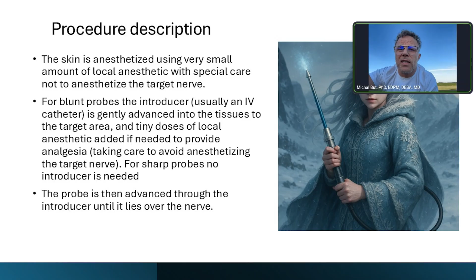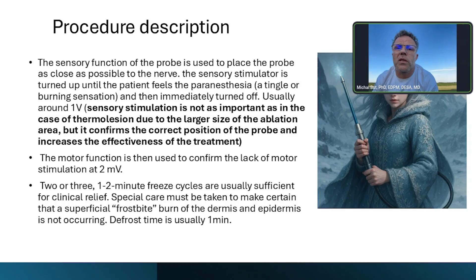And use the stimulation, especially when you start with the procedure. I encourage you to use the stimulation to confirm the correct placement of the probe, because if there is a stimulation below zero point 0.8 volt, you are 100% sure you are close enough to freeze the nerve completely, because that gives you information that the nerve is as close as 2 millimeters to the probe. So if you have stimulation over 1 volt, you need to change the position of the active tip and try to stimulate again. If you're not sure, if you are close to the motor nerve, like a nerve root, use motor stimulation to exclude proximity to the nerve root. And the next, of course, 2 cycles, 2 minutes with 1.5 minute defreeze times.